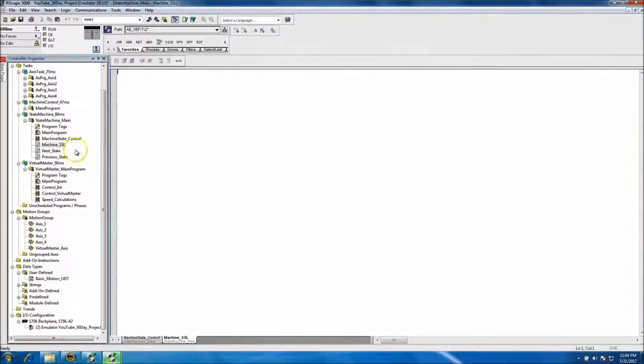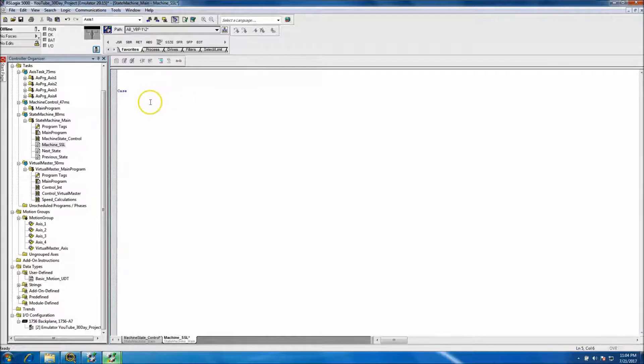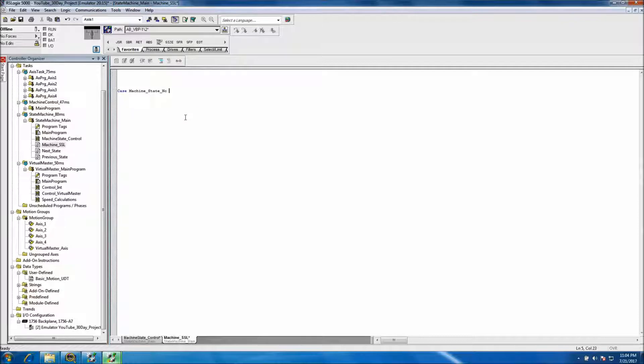At this point we want to go ahead and add our Structured Text. This will be a CASE function, so let's go ahead and put CASE. In this instance we want to put the machine state number, and I'll show you that. We'll go in, pick up the tags we already have made — machine state number — and put it in the CASE of machine state number, then we'll say zero.